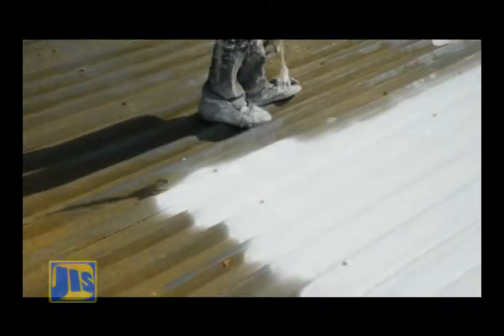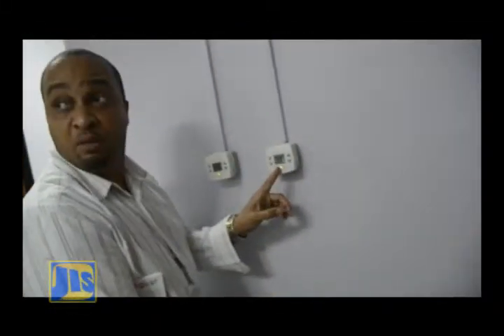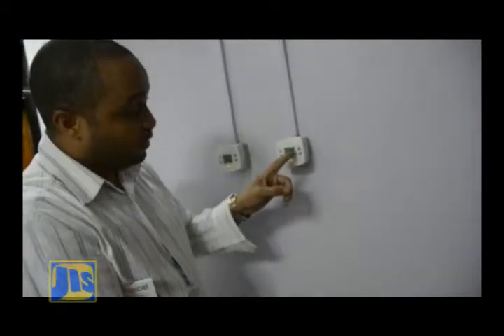So the impact on your energy consumption is going to be significant. And the savings don't stop there. The solar film that we have applied to the windows, it's not just color tinting. It will reduce the solar radiation coming through the window by approximately 70 to 80%. And that will have a direct impact on the air conditioning load. Having done the building envelope retrofits, the air conditioning needs would be considerably lower now that the buildings are much cooler. So the next step is assessing the current air conditioning configuration, and where there is inefficiency, corrective measures are taken. And if we can replace many of the current old inefficient units, we expect to see approximately 30 to 40% saving in the air conditioning demand for electricity.